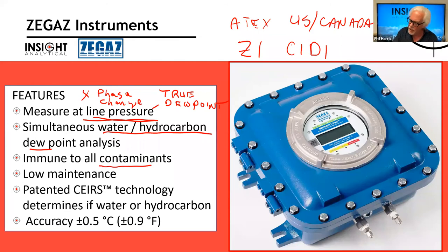It is immune to contaminants. Sometimes other things are going to condense in our system, like methanol or glycol. With the way ZEGAZ does the dew point measurement, even if those things start to condense, they don't detect those as a water or a hydrocarbon dew point. Very low maintenance, no moving parts, patented technology. And high accuracy on the dew point, about a half a degree C. So we're going to talk a little bit about how this works.